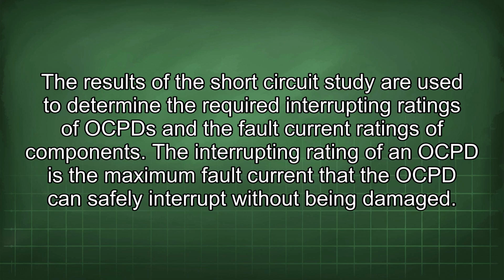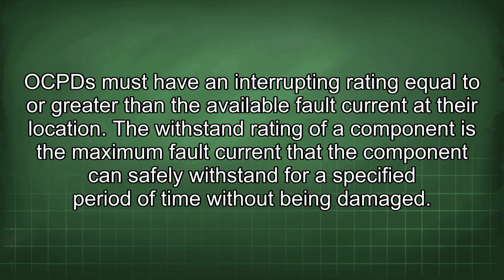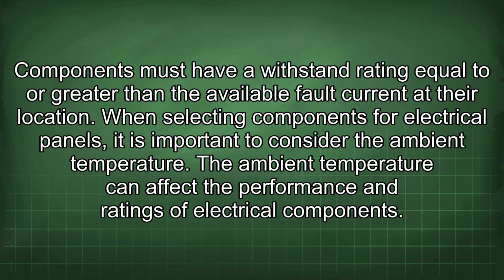The results of the short circuit study are used to determine the required interrupting ratings of OCPDs and the fault current ratings of components. The interrupting rating of an OCPD is the maximum fault current that the OCPD can safely interrupt without being damaged. OCPDs must have an interrupting rating equal to or greater than the available fault current at their location. The withstand rating of a component is the maximum fault current that the component can safely withstand for a specified period of time without being damaged. Components must have a withstand rating equal to or greater than the available fault current at their location.